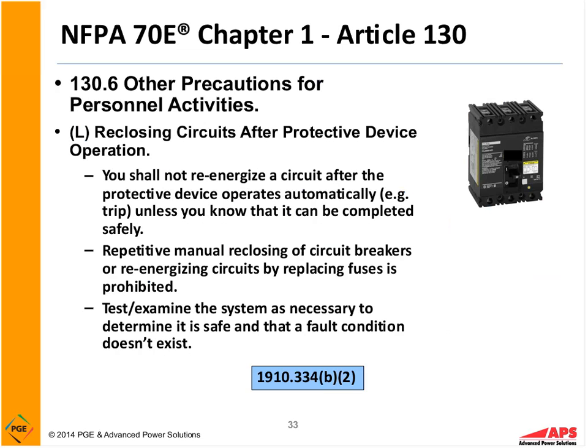Okay, so reclosing breakers. A lot of times we'll have folks that will reclose breakers. So a breaker will trip and they'll go up and reset that breaker. Now if you have not tested the circuit to verify that it's safe to do so, that's actually against OSHA regulations. So in other words, if a breaker trips, what they're saying is if it's an overload, in other words, you plugged too many things in or a motor jammed up and you cleared that and you know it can be done safely, okay, then it's okay to reset that breaker.